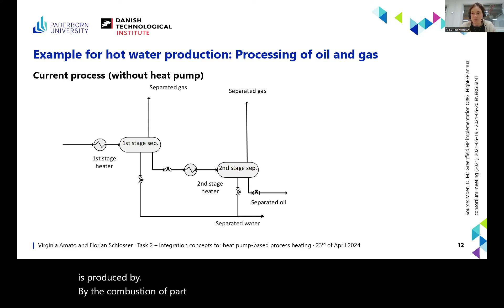While integrating a heat pump, there are different possibilities. The condenser of the heat pump can directly serve as a heater for the process, and since the oil and gas need to be cooled after the process, the cooling acts as the heat source for the heat pump. In this concept, the heat pump is integrated at process level, which has its advantages, because the temperature lift is more limited, and therefore it needs fewer compression stages and allows more refrigerant choices. But it's of course a tailored integration that is more complicated to design.